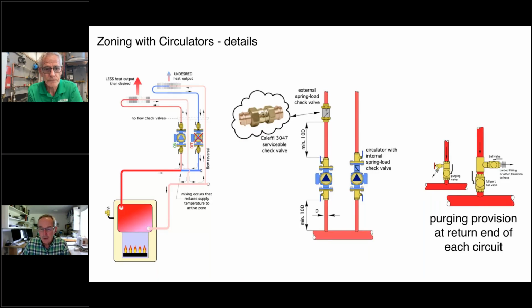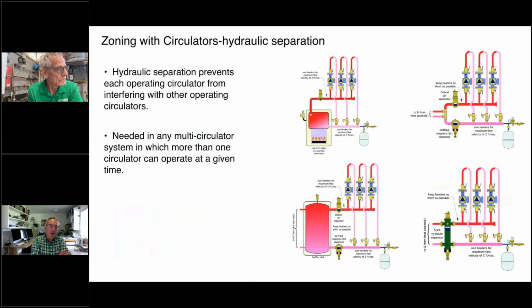Yep, very good. And then, earlier we talked about hydraulic separation. And what is it? Well, anytime you have two or more circulators that can operate simultaneously, and that's certainly possible with zones, we don't want them interfering with each other. The key concept to achieve hydraulic separation is to identify what we call the common piping. In this case, it would be the supply header, in this case, a cast iron boiler, and a return header. Those pipes are essentially common to all three circuits.